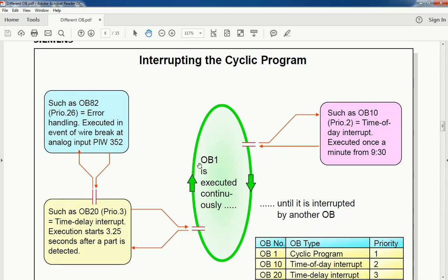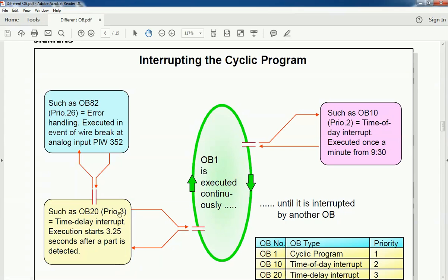OB1 is executing continuously as per its period. Meanwhile, when an error comes from the PLC, OB82 — which has the highest priority of 26 — will execute and hold the main OB, perform the OB82 instructions first. The second priority is the time delay interrupt, priority number 3, so OB20 will execute, OB1 will hold, and after OB20 executes, OB1 resumes cyclically. Next, the time-of-day interrupt will also execute in this cycle.